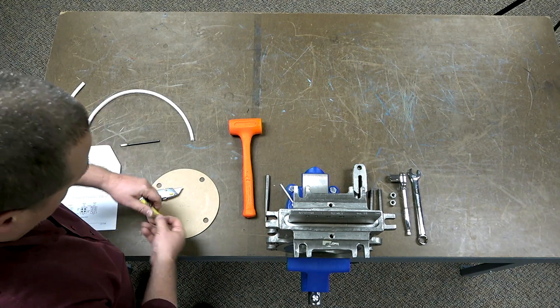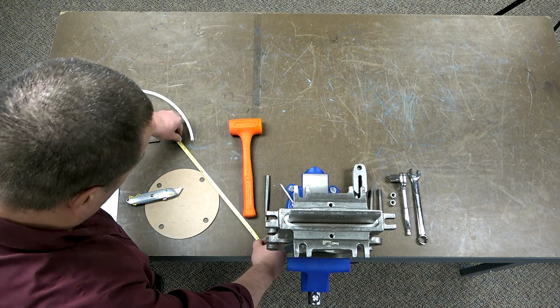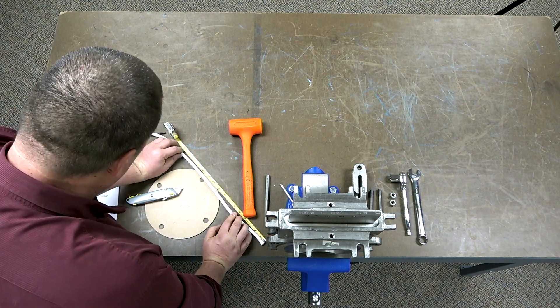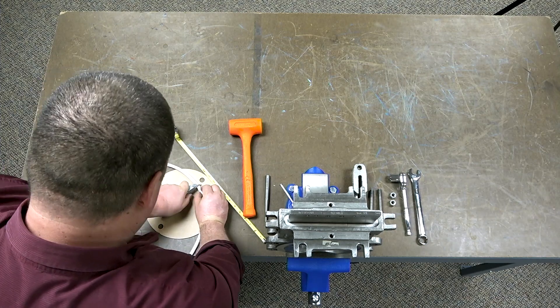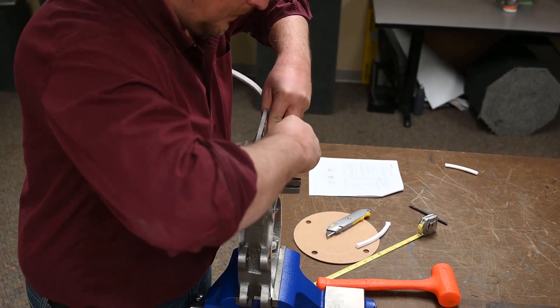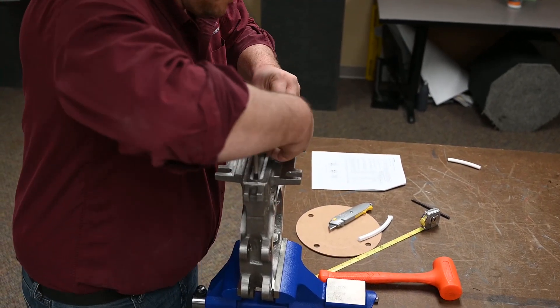Next, measure and cut the last layer of packing. Wrap the last layer around the gate with the joint staggered from the previous layer and tamp it down with the square end punch and rubber mallet.